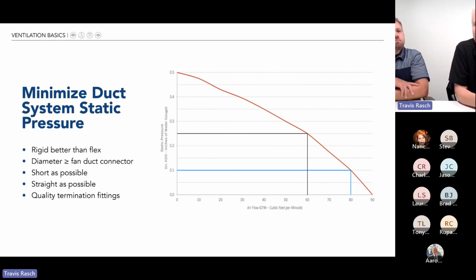I'll talk quickly about static pressure. This is very important when you're talking about ventilation, be it a bath fan, a range hood, or an HRV, ERV, supply fan, any type of mechanical ventilation. So static pressure is resistance to airflow as air is trying to move through a duct. So what we're looking at here, that red curve is called a fan curve. You can see on the vertical axis is our static pressure measured in inches of water gauge, and on the horizontal axis is CFM.